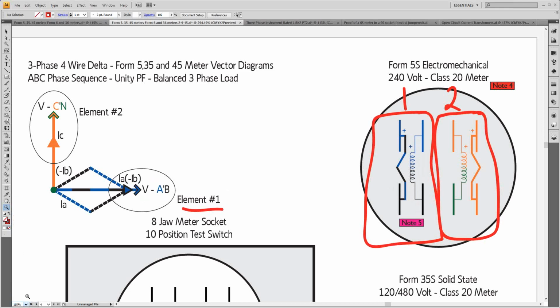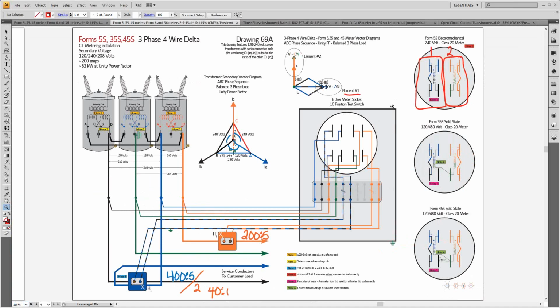Just so we can see and prove that, from the blue and black conductor, which is the voltage across that potential coil, between blue and black, as I look right there, there's 240 volts between those two. So blue to black really ends up being the voltage across this coil right here. This is a 120/240 volt secondary coil that's connected in a series connection, so I end up with 240 volts across there. From A to B shows 240 volts here also. So that's what that coil is, that vector, and its magnitude is 240 volts, the same voltage across this element in my meter.